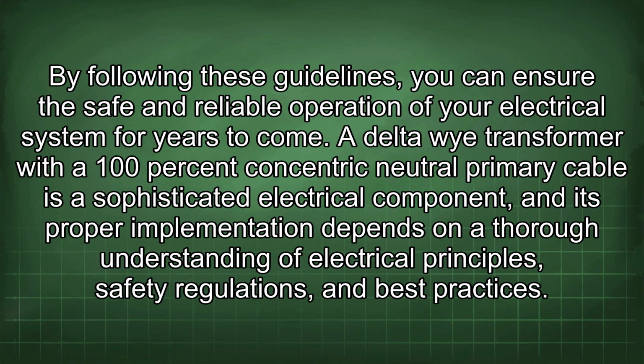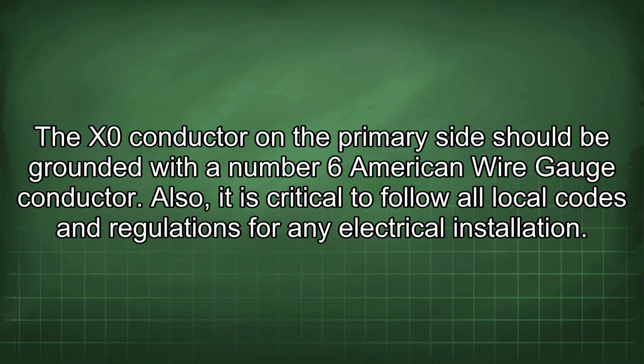A Delta-Wye transformer with a 100% concentric neutral primary cable is a sophisticated electrical component, and its proper implementation depends on a thorough understanding of electrical principles, safety regulations, and best practices. The X0 conductor on the primary side should be grounded with a number 6 American wire gauge conductor. Also, it is critical to follow all local codes and regulations for any electrical installation.